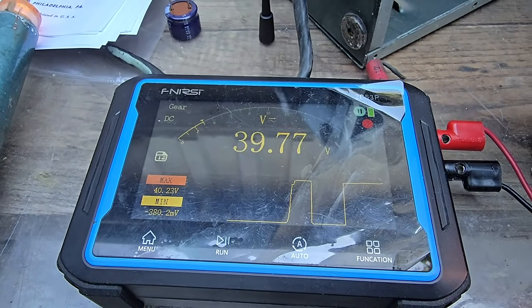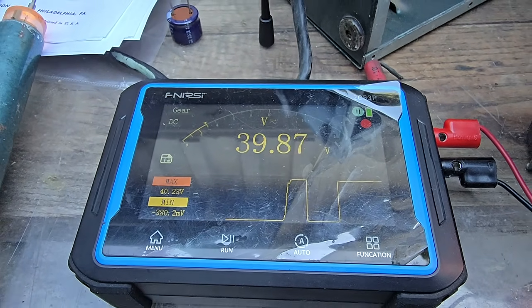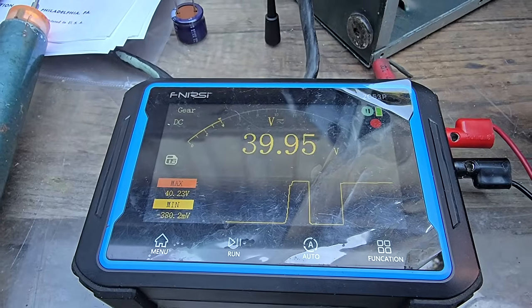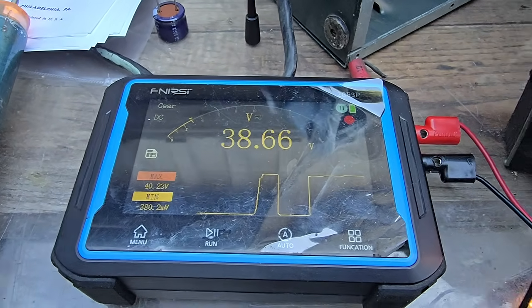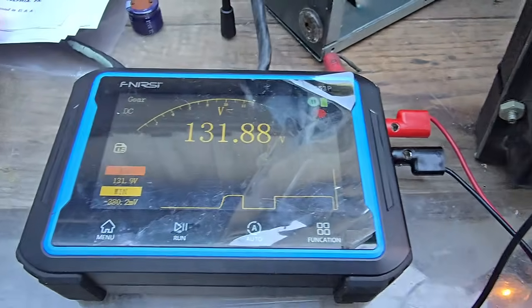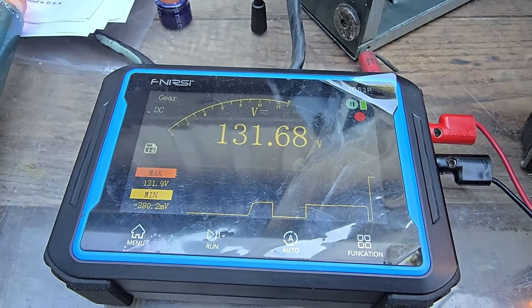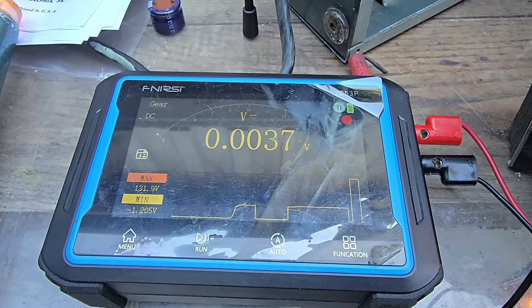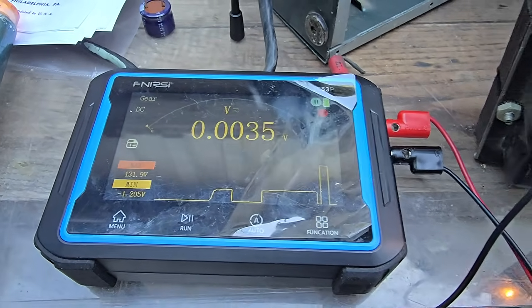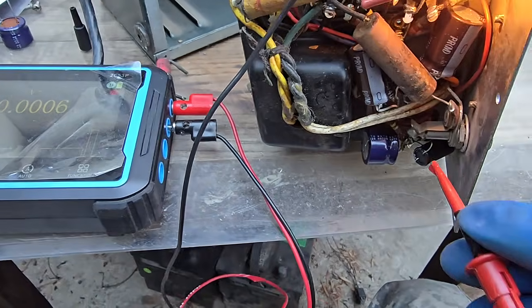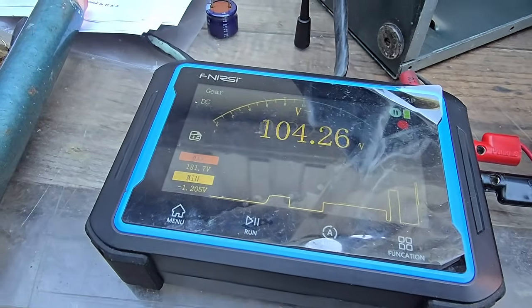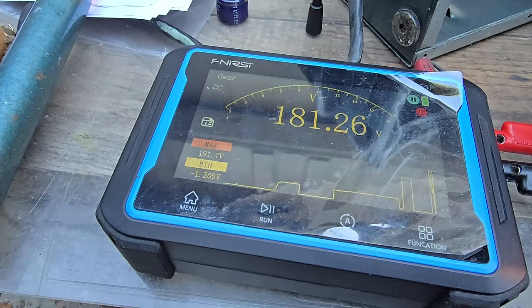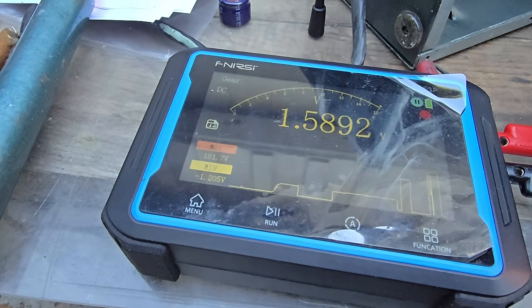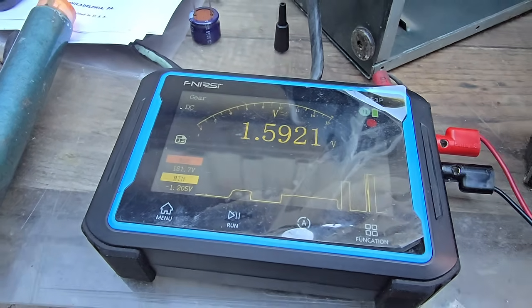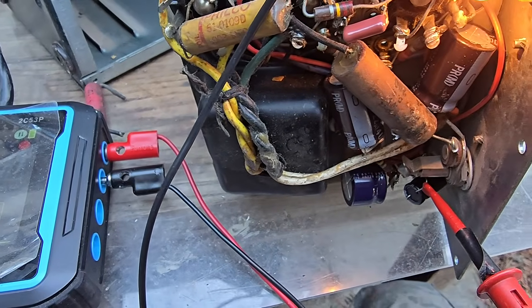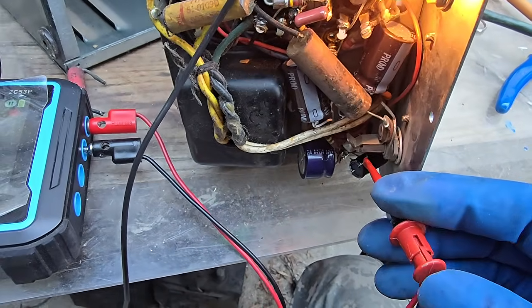Okay, well, we didn't quite get up to the 50 volts that the schematic says on the probe tube, but we're a lot closer than we were, so I'll have to take that. Let's see about our leakage here. We got 131 here, which is really kind of high, and we got 0 there. That's good. So it's kind of weird. Got 181 there now. We got 1.5 there. That's on that bypass tube. That's actually right.